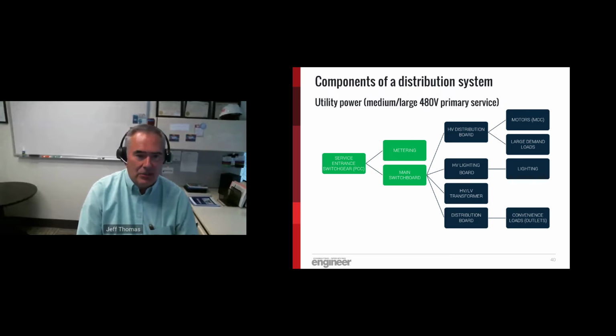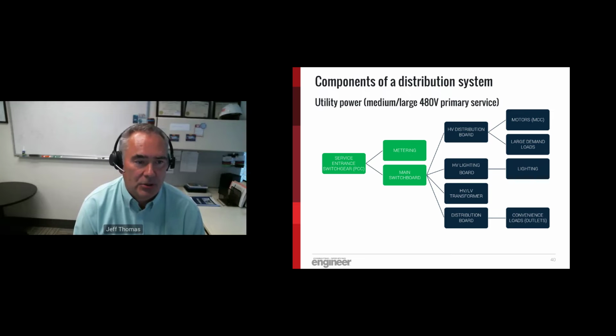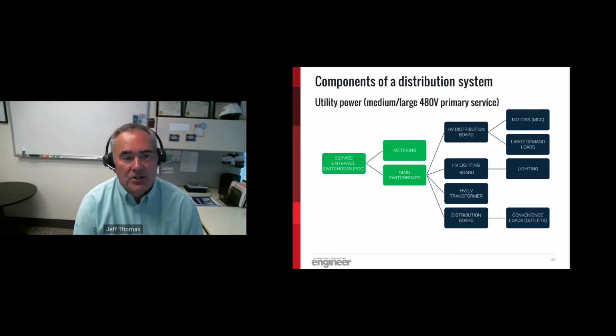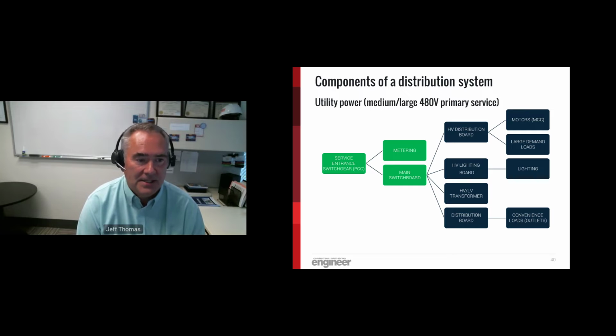So in this slide, you can see a high-level tree of our electrical distribution system. We start with service entrance switchgear, something called the point of common coupling, or the PCC. This is where we connect to the utility. Everything to the left, which is not shown in this slide, would be the responsibility of the utility. Everything to the right is ours. So this shows a medium to large 480 volt primary service installation. We come in from our switchgear, there's some sort of metering because the utility is not going to do it for free. We've got a main switchboard, which would then break off into a variety of distribution boards.